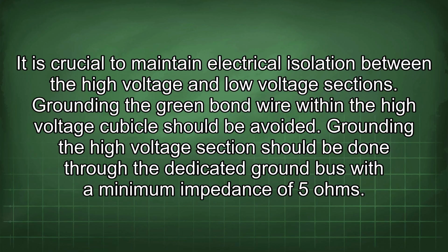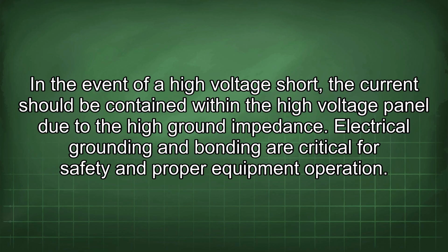Grounding the high voltage section should be done through the dedicated ground bus with a minimum impedance of 5 ohms. In the event of a high voltage short, the current should be contained within the high voltage panel due to the high ground impedance. Electrical grounding and bonding are critical for safety and proper equipment operation.